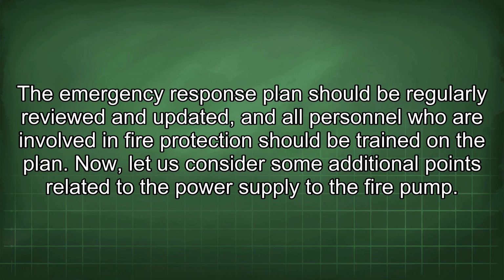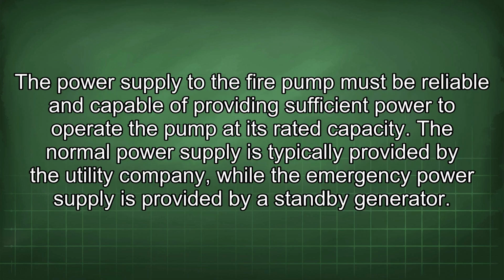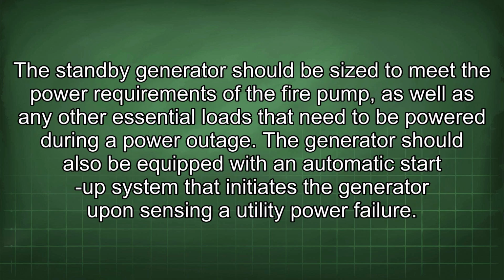Now, let us consider some additional points related to the power supply to the fire pump. The power supply to the fire pump must be reliable and capable of providing sufficient power to operate the pump at its rated capacity. The normal power supply is typically provided by the utility company, while the emergency power supply is provided by a standby generator. The standby generator should be sized to meet the power requirements of the fire pump, as well as any other essential loads that need to be powered during a power outage.